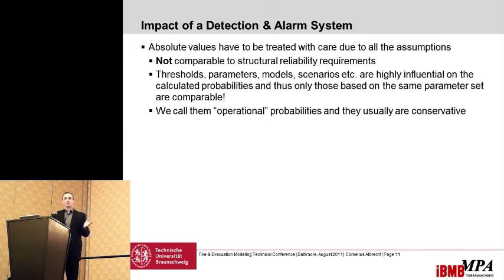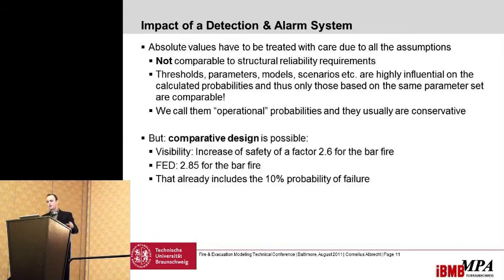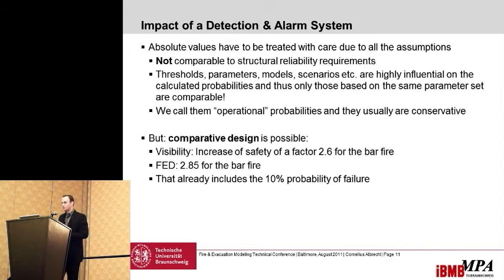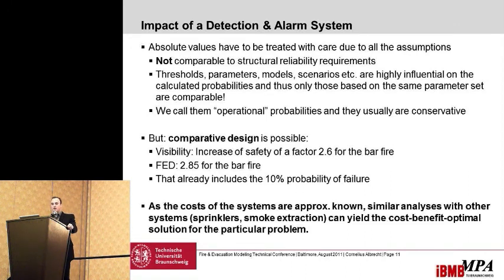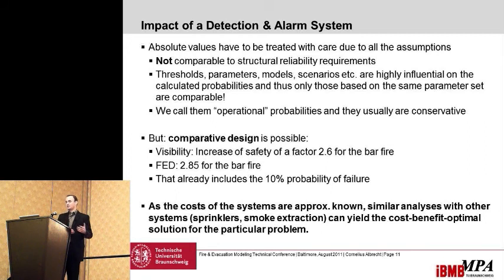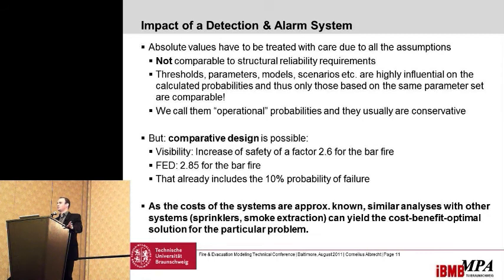What I can extract from this is a comparative design result: for visibility, there is a safety increase of a factor of 2.6 for the bar fire, and even 2.85 for the bar fire using the FED criterion — already including a 10% system failure. As I know approximately the costs of the system, I can compare it to other systems such as sprinklers or smoke and heat extraction systems, find their costs, and compare them. This means I can find the cost-benefit optimal solution for the particular problem.